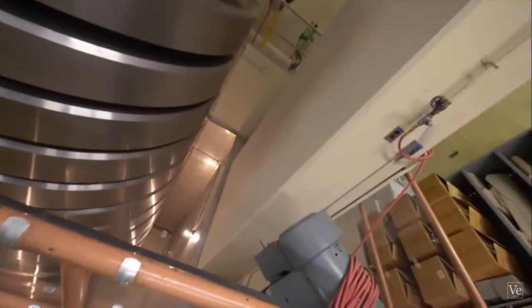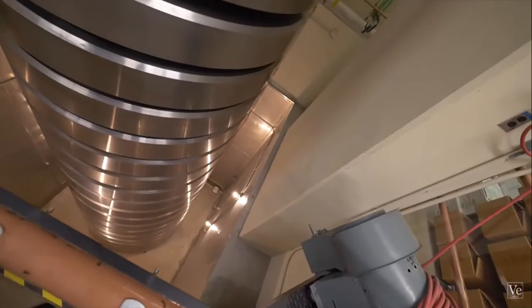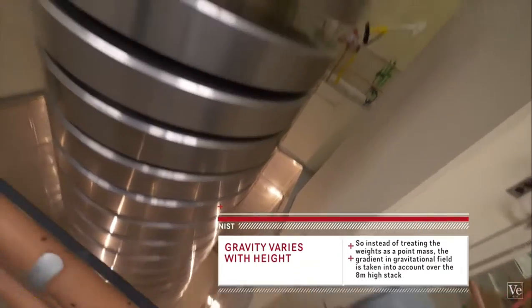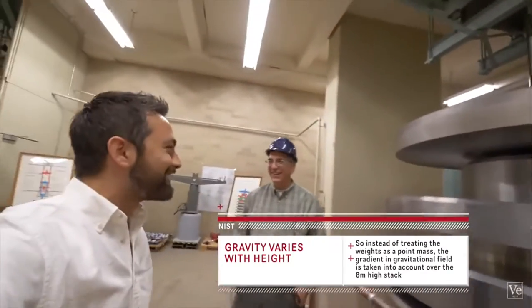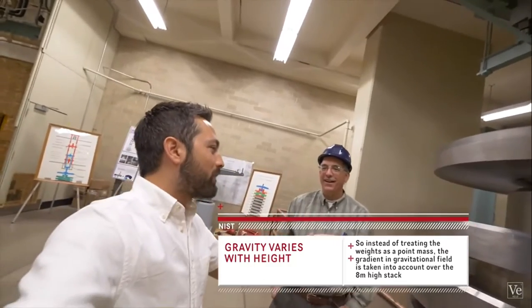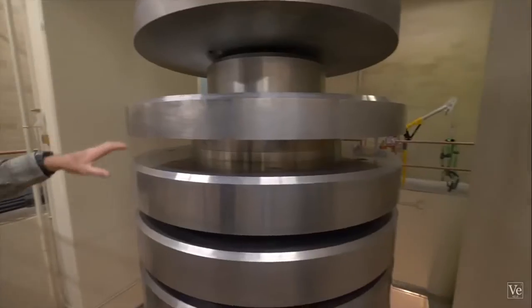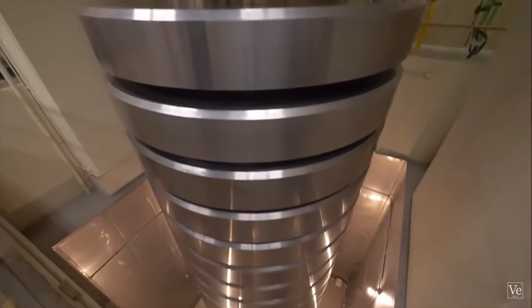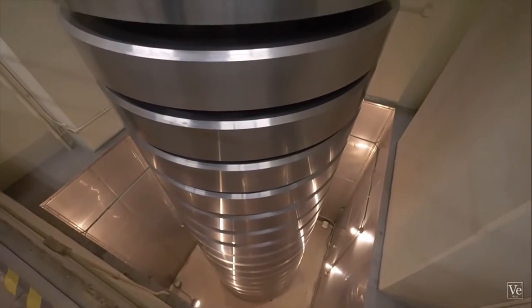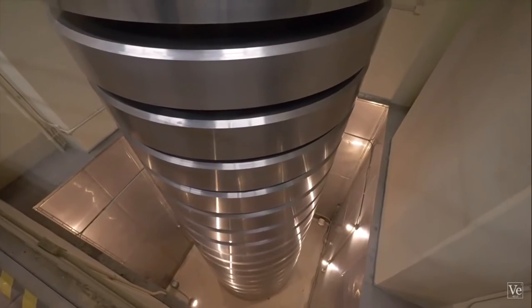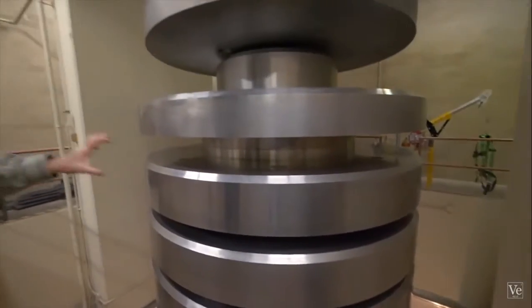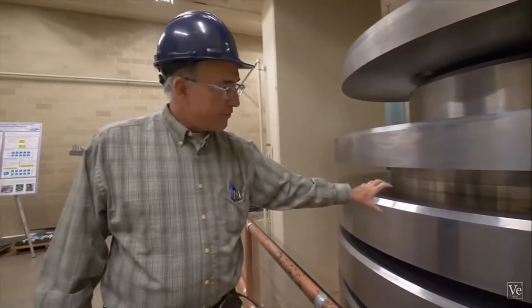Not only does that mean the masses have to be accurately calibrated, it also means the gravitational acceleration at this location has to be taken into account. It's actually slightly less than Earth's standard gravity, so an additional 600 pounds are required. Plus, the buoyant force must be counteracted. Since these masses displace 125 pounds of air, a further 125 pounds must be added to reach 1 million pounds of force.